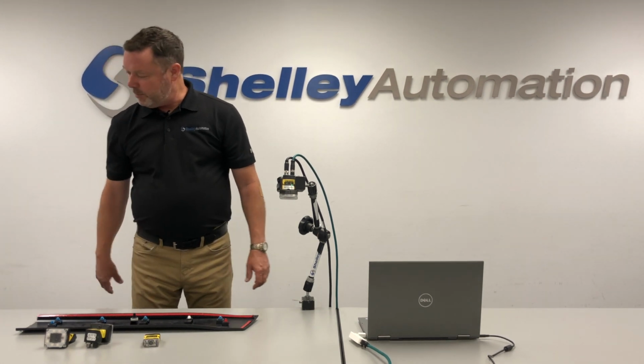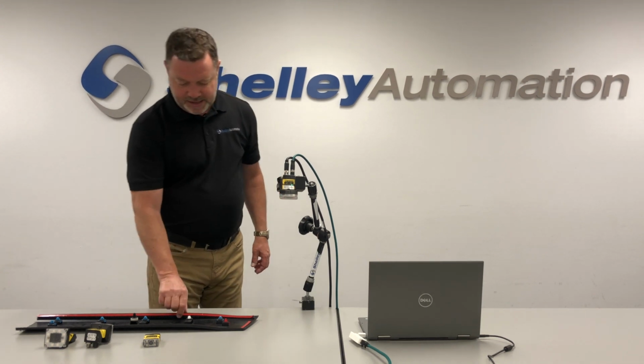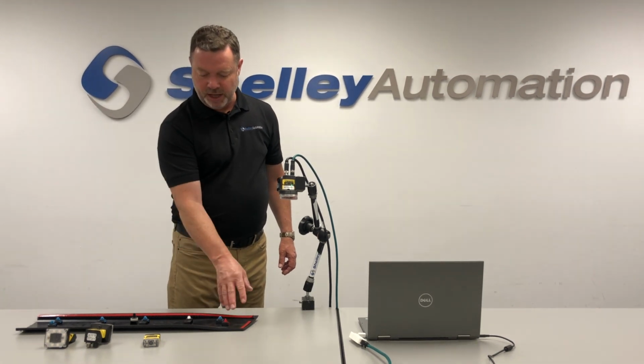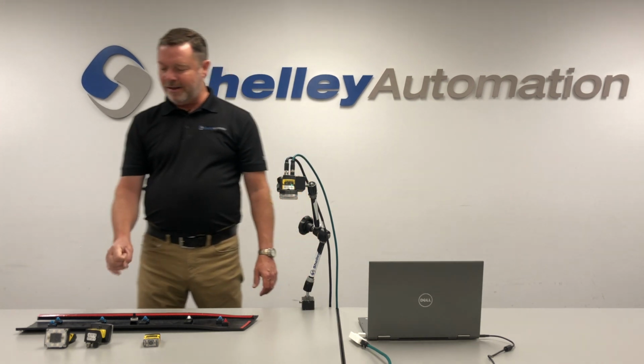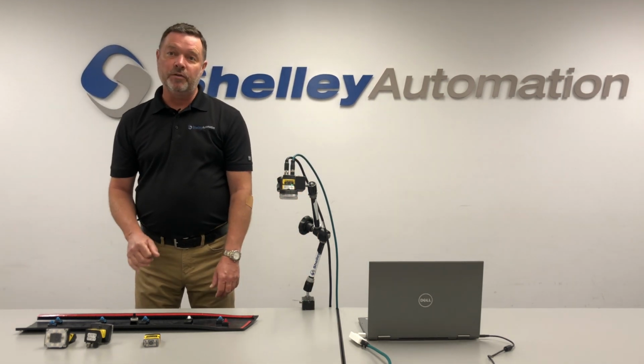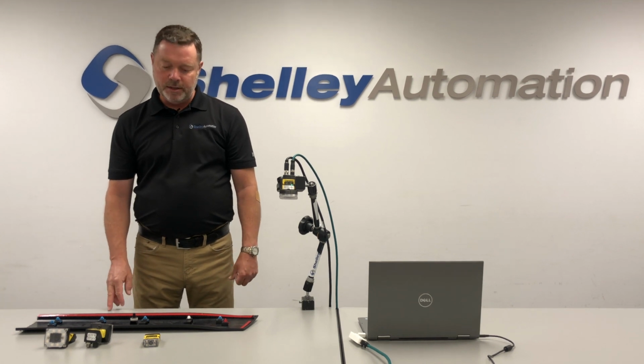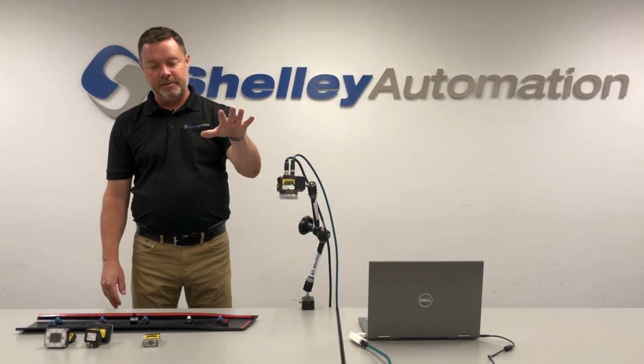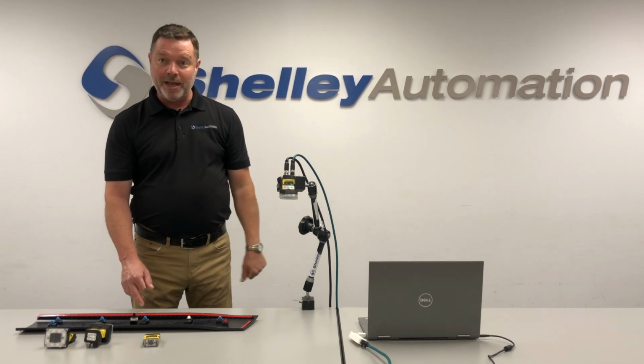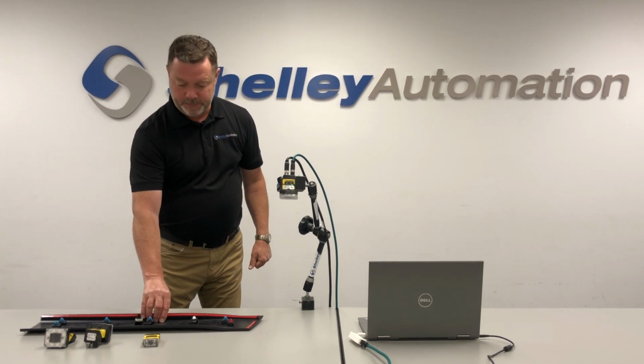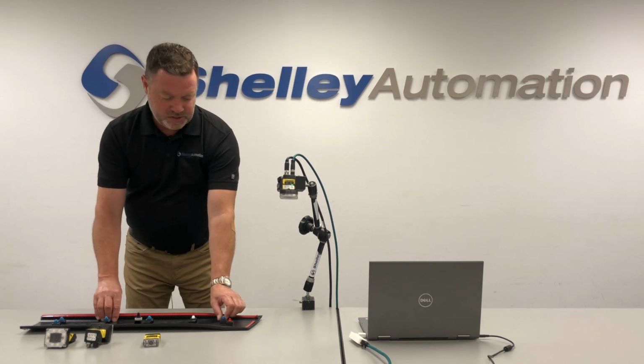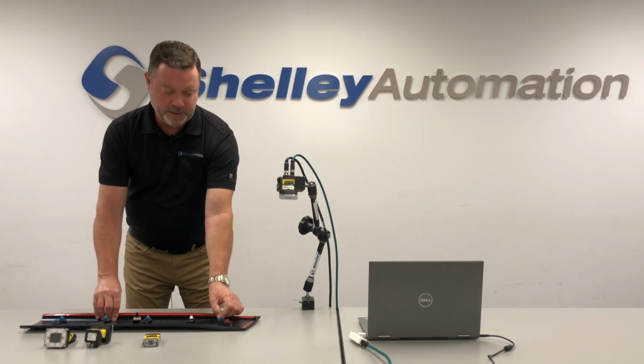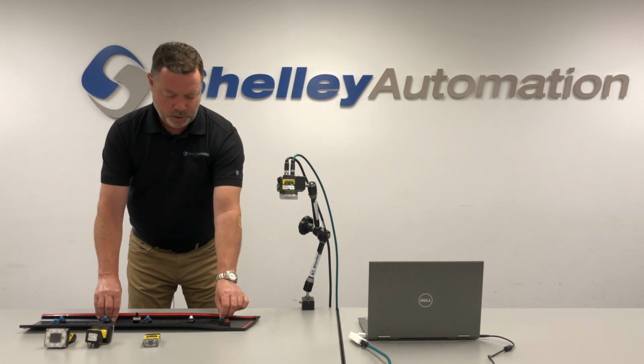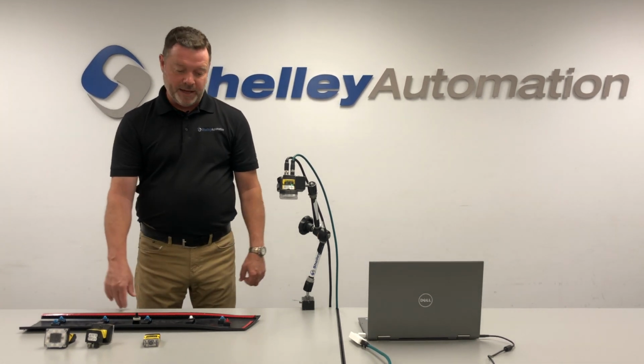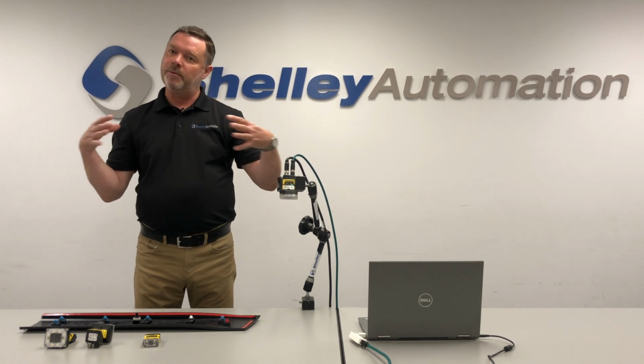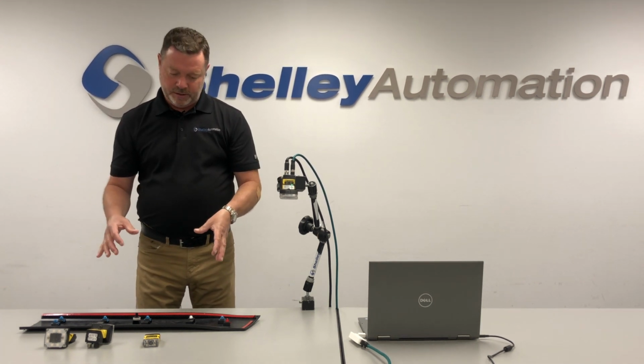So the application I'm going to show you today is to detect the presence of these clips as well as the color of the clips. An advantage of a color vision sensor over a color photoelectric sensor is you can do a much larger standoff. We can also locate the part in case you get a bit of movement of the part. And we can set up a sensing window that can accommodate movement in the feature, in this case the clip. Whereas if we just use the photoelectric sensor, we'd have a very small point and the part would have to be very accurately fixtured.